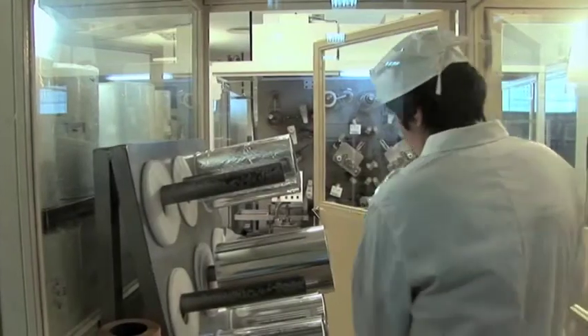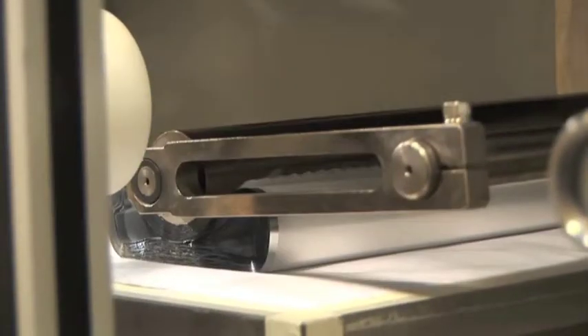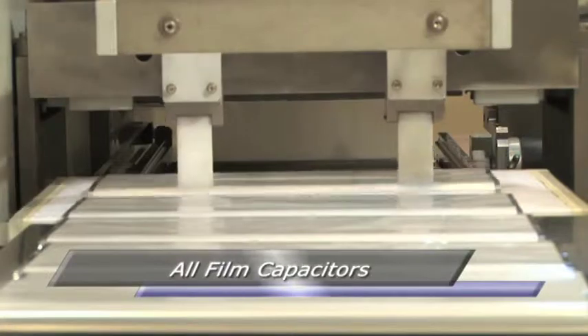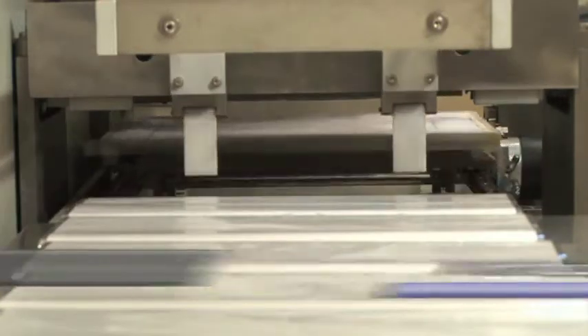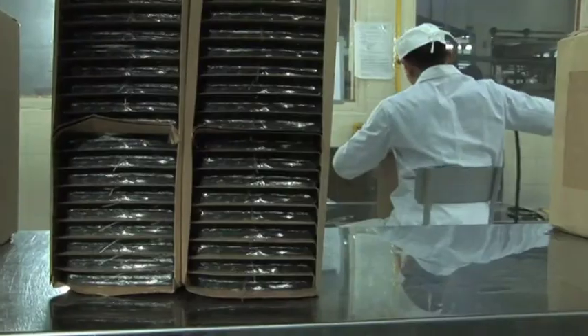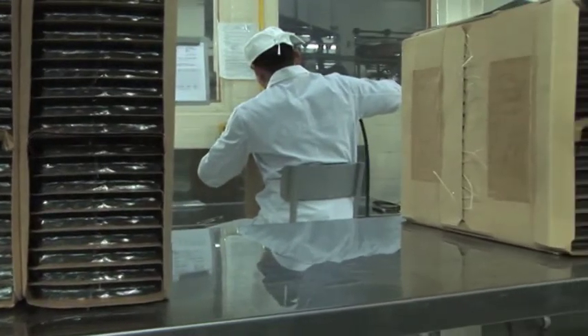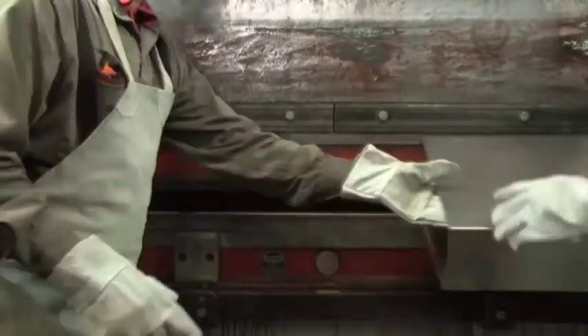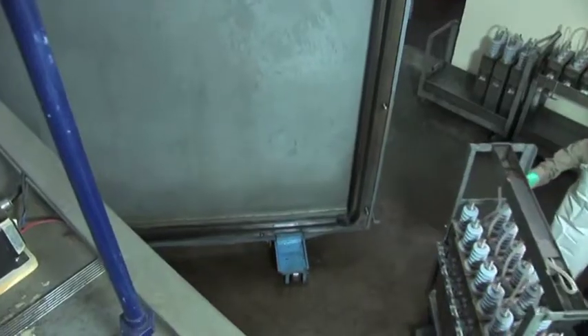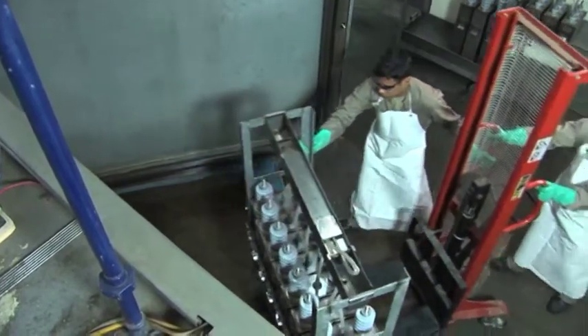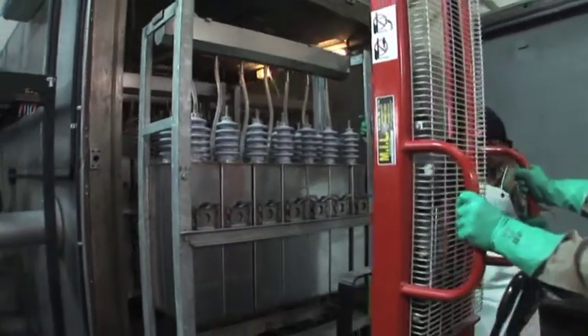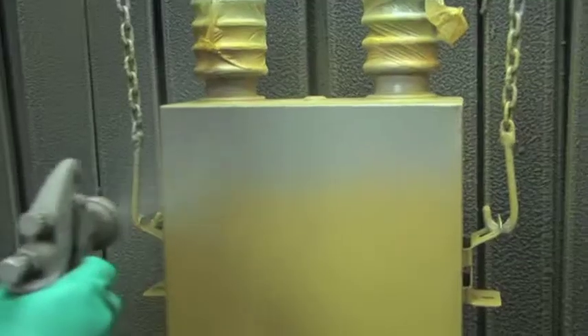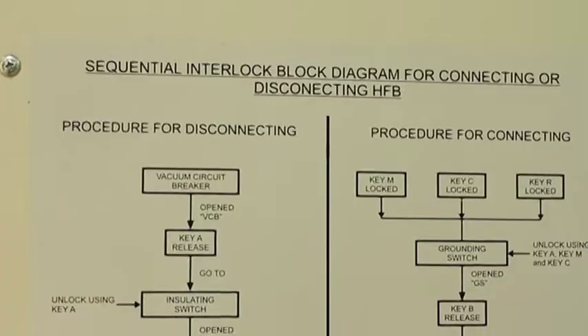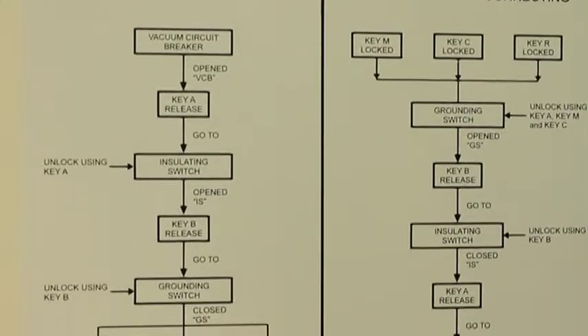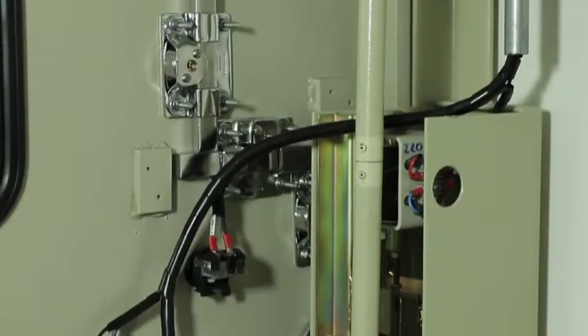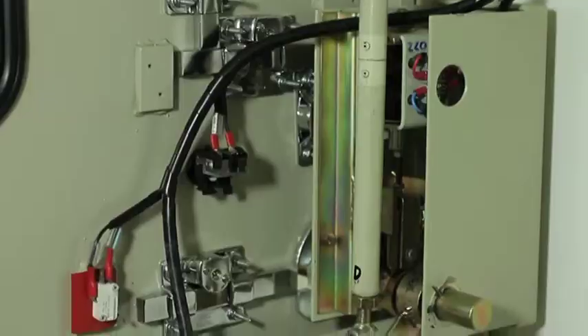Each stage is composed of environmentally compatible all-film capacitors impregnated with PCB-free biodegradable oil with internal fusing. Capacitors in each stage are connected in double Y with ungrounded neutral and are operated by a 3-pole vacuum circuit breaker, which guarantees a restrike-free operation. The stage can be disconnected for maintenance by means of a 3-pole disconnector switch with 4-pole grounding blades.